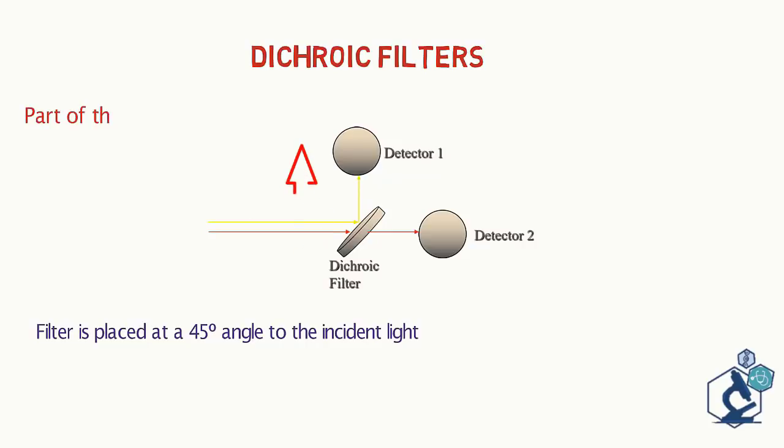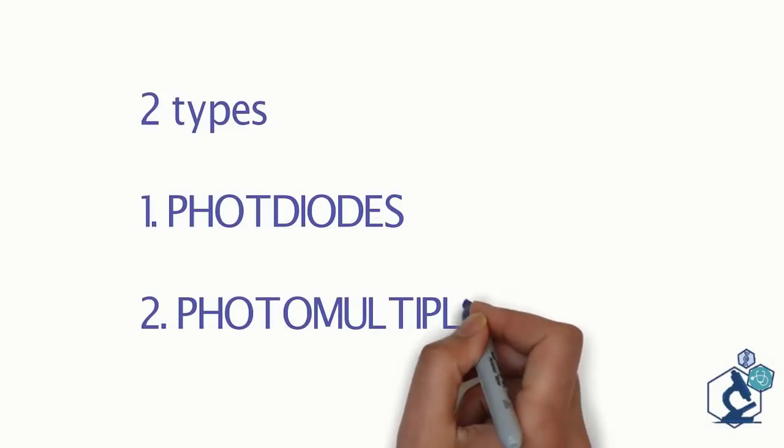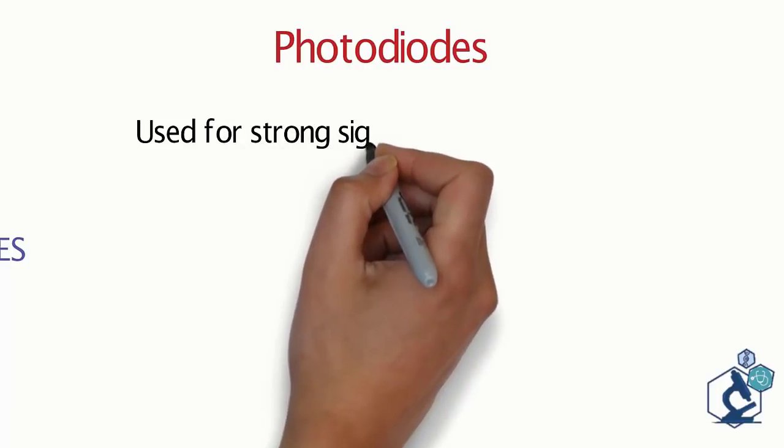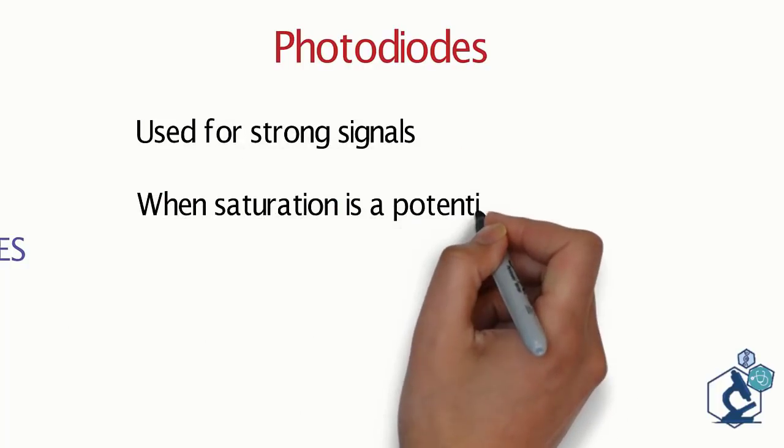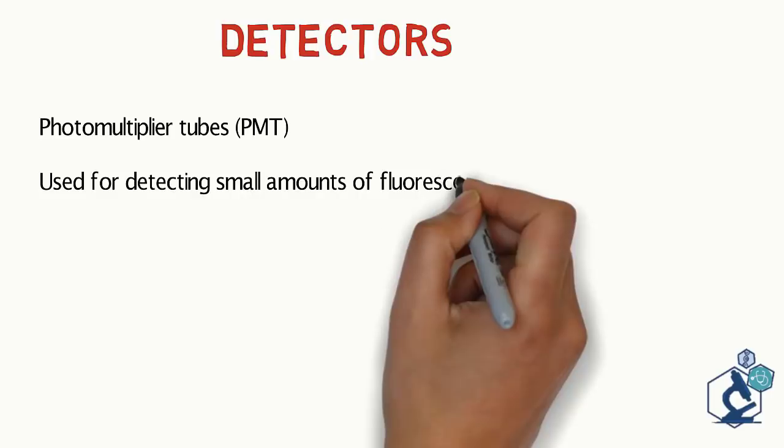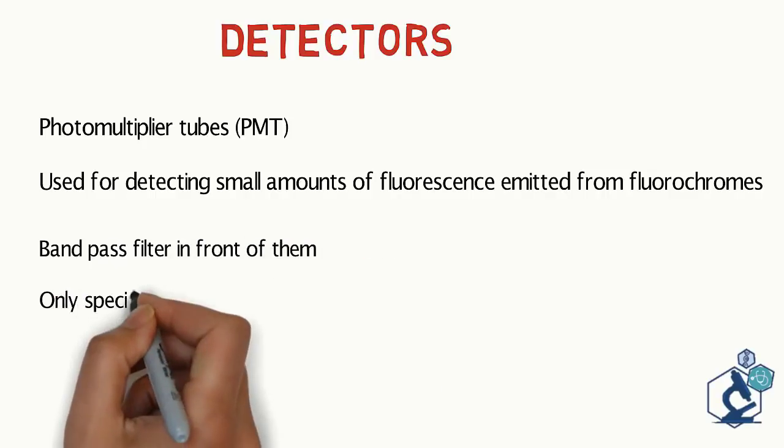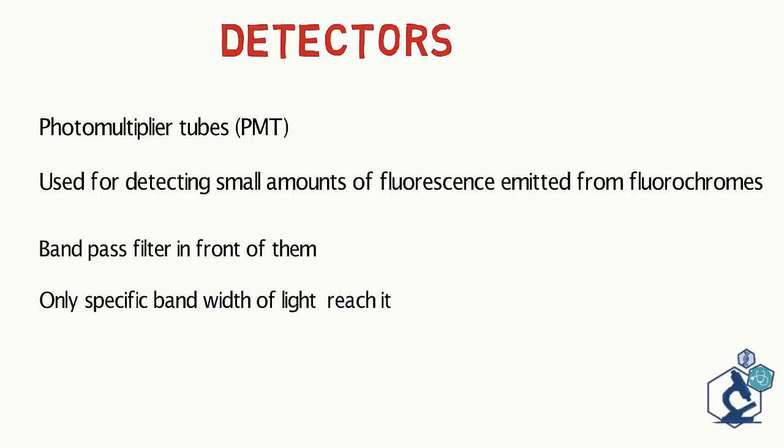Dichroic filters. Dichroic filters can be a long pass or short pass filter. They are placed at a 45 degree angle to the incident light. Part of it is reflected at 90 degrees to the incident light and part of the light is transmitted and continues. Now coming to detectors. There are two main types of photodetectors used in flow cytometry. Photodiodes which are used for strong signals when saturation is a potential problem, e.g. a forward scatter detector. Photomultiplier tubes or PMT, more sensitive than a photodiode. A PMT is used for detecting small amounts of fluorescence emitted from the fluorochromes. Photodetectors usually have a band pass filter in front of them to only allow a specific bandwidth of light to reach it. Therefore, each detector has a range of light it can detect once a filter has been placed in front of it.